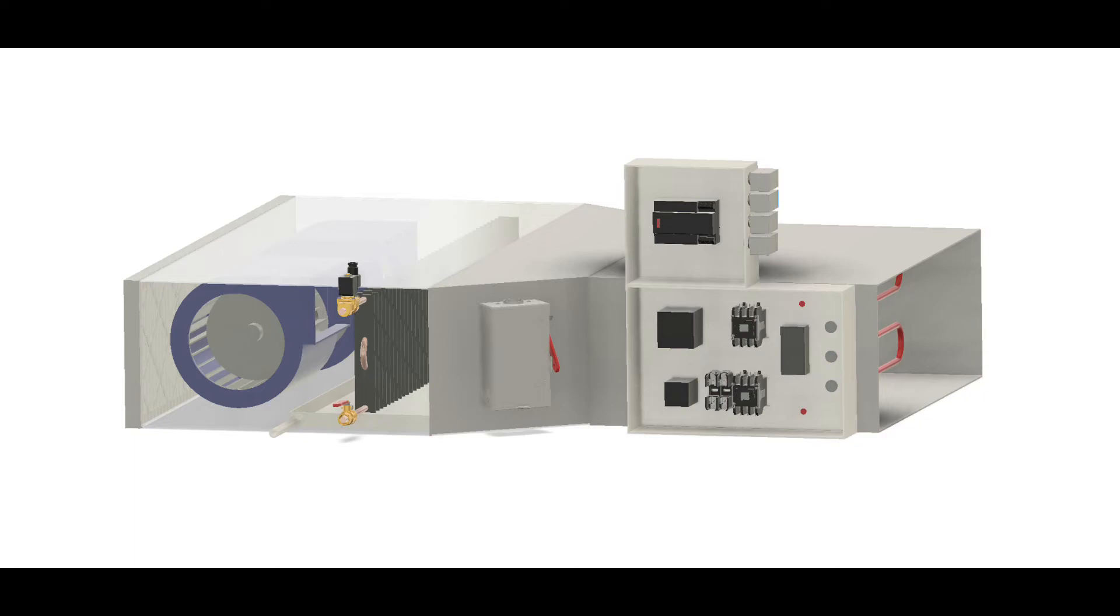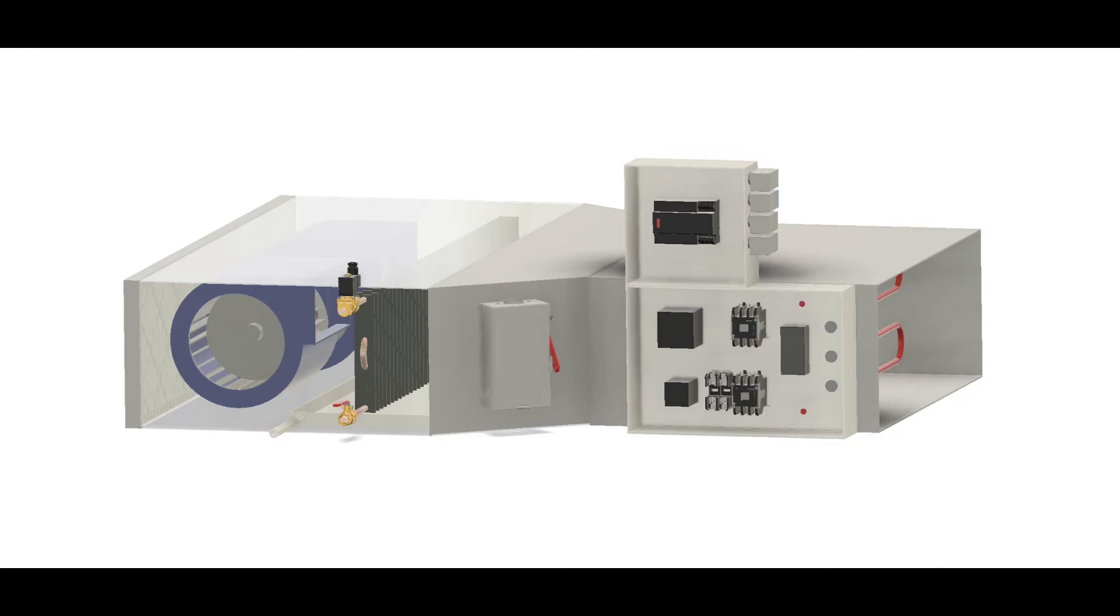Also, is the blower fan running? The blower fan needs to be running in order for the air pressure switch to close and allow the control circuit to be completed, because the heating elements cannot be on if that blower motor is not running for obvious safety reasons.